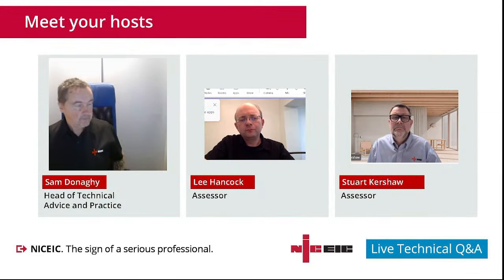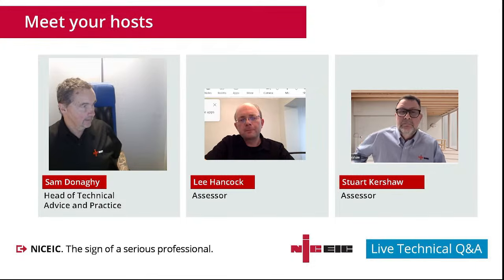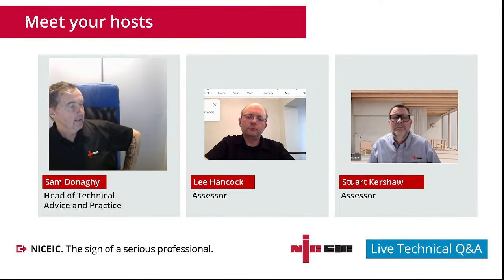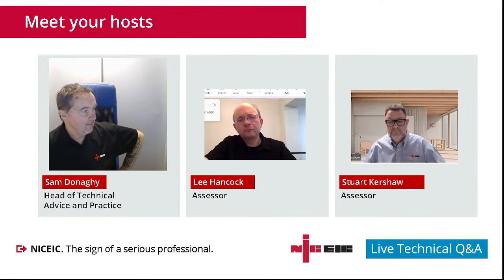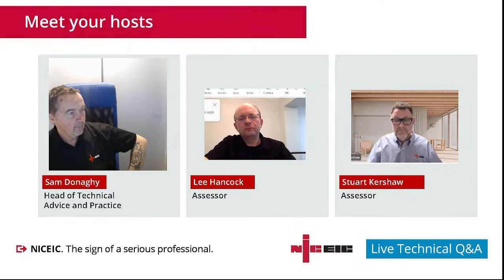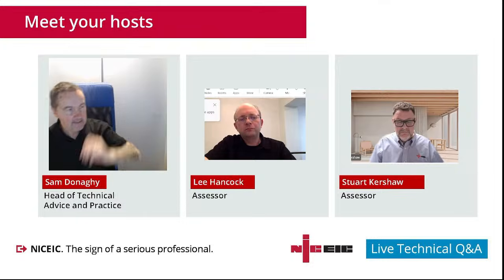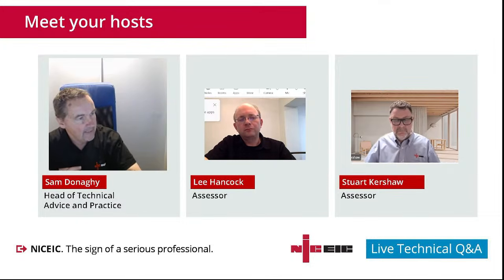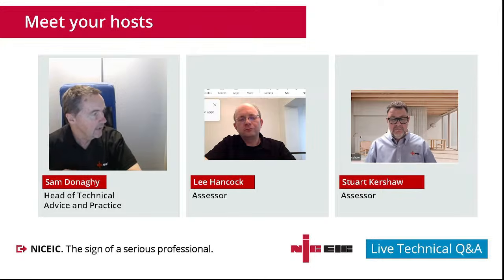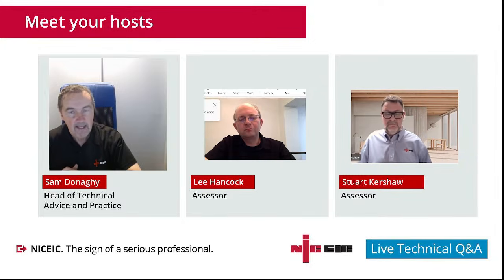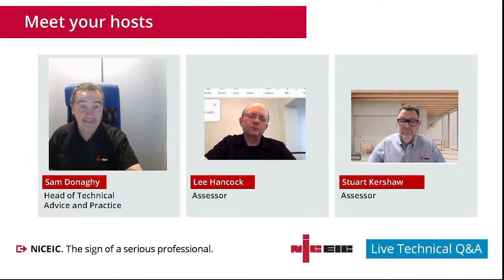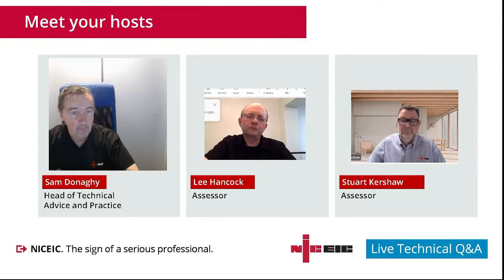Okay. So we'll take a few questions that have come in. The first one I'm looking at is from one of the engineers tonight. When installing Type 1 SPDs without having access to the lightning protection risk assessment, and being an electrician not fully conversant with BS EN 62305, who is the designer of the installation on the EIC in relation to the Iimp value of the SPD, even if you have selected the overcurrent protective device and cable size? An SPD and lightning protection system question. My first thought is that the designer of the electrical installation could well be the electrician, but they may need that expertise from a lightning protection system expert.